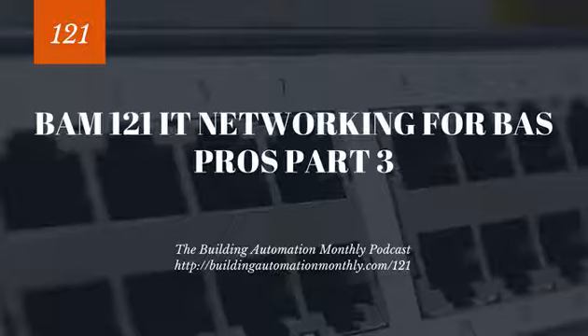So we have public and private. Private is usually what you're going to be dealing with as a BAS professional. And you're typically going to be asking for a set of IP addresses, a range of IP addresses. That's why it's so important to understand that when you need 120 IP addresses, you may ask for a /25 subnet. That would give you 126 host addresses when we account for our default gateway and our broadcast address. In which case, you may say, hey, I want static IP addresses, which is the general preference in the world of BAS.